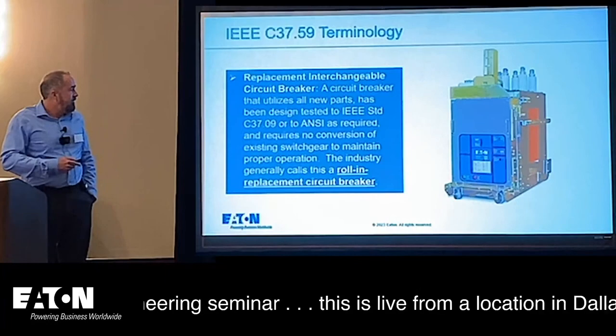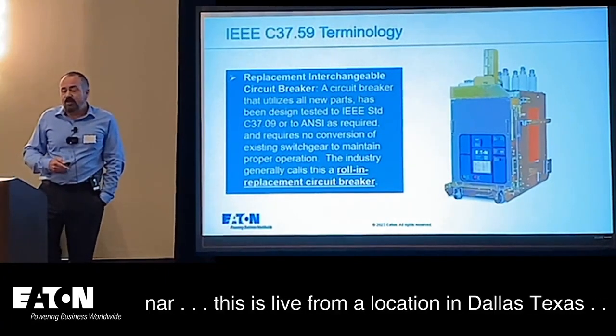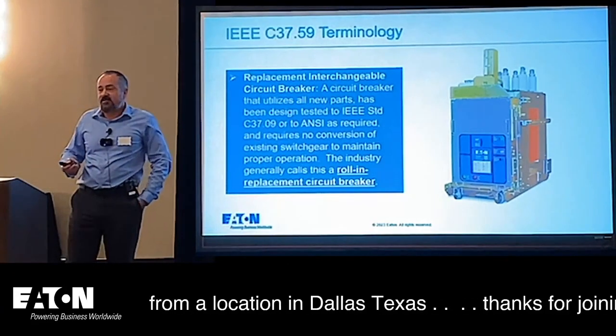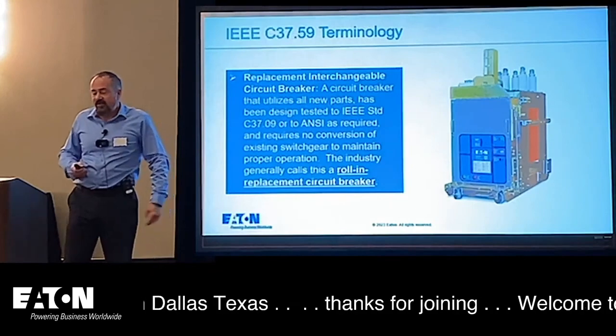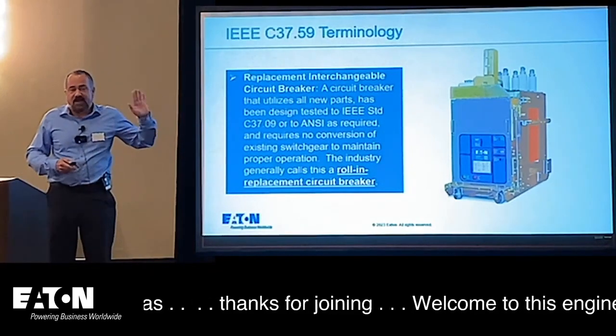Design verification is another term defined in C37.59 — it's a process of design qualification in accordance with appropriate standards. Design testing is very different from production testing or preventive maintenance tests. One tactic I've seen is companies doing these conversions and testing to NETA ATS standards, but that's not acceptable. NETA ATS is a maintenance standard — it's not a valid test for verifying the operation of something where you've done a complete design change.